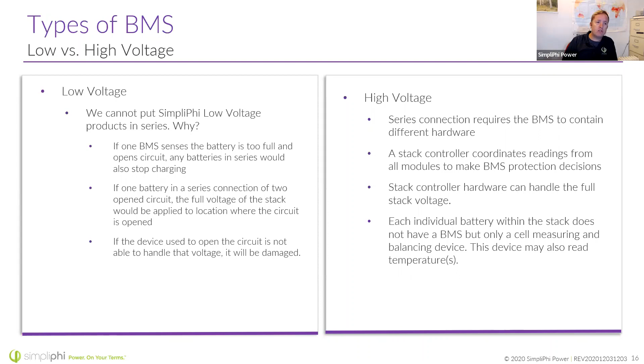Now, in high voltage situations, when you have a bunch of batteries stacked with a stack controller on top that's been designed to work with that high voltage and can handle the full stack voltage, each individual battery isn't going to have an internal battery management system. You're going to have one for the entire rack. I have a picture of that later in the presentation where we can take a closer look. So it's different hardware between the high voltage and the low voltage setups.